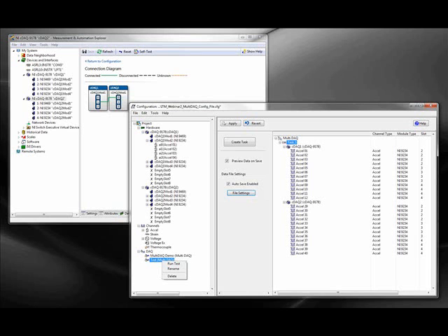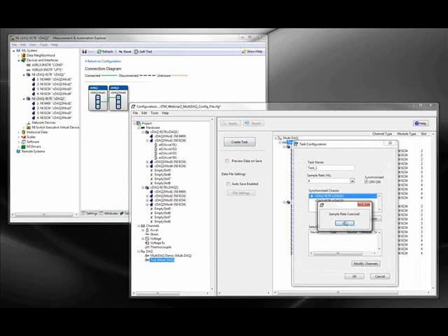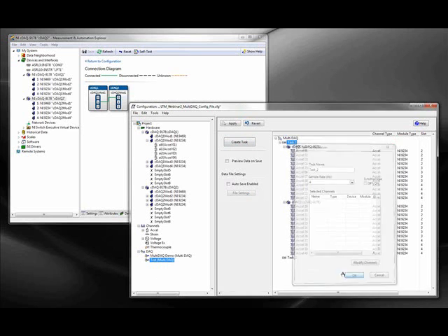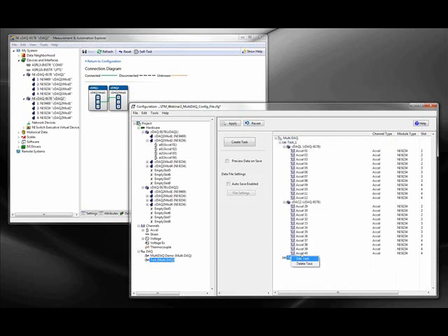There's another thing I could mention here, when you're creating your tasks, you can have multiple tasks. So we could create another, and we could call it task 2. What we'd have to do is have available channels. You can have multiple tasks with channels collecting data at different sample rates. The one thing is the two tasks would not be synchronized. To have synchronous data, it has to be all under one task.